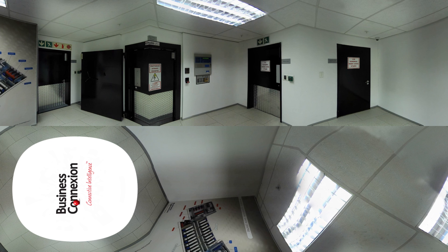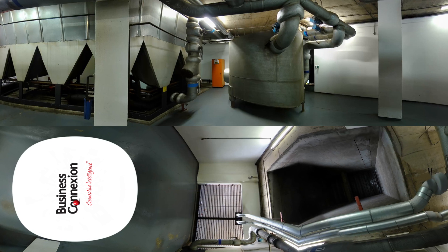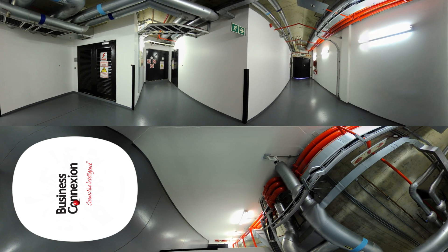As part of its Tier 4 certification, the Global Uptime Institute requires any data center to have access to water from two different suppliers. As this is not possible in South Africa, we have designed a unique closed-loop chilled water system which was approved by the Uptime Institute. The water supply is piped through a central corridor, which makes water ingress into the computer rooms impossible. Water stored in the reservoir and supplied from the municipal water supply supplements the gas fire suppression system, but all pipes into the various sections of the building remain completely dry until needed to prevent any possible water damage to critical equipment.